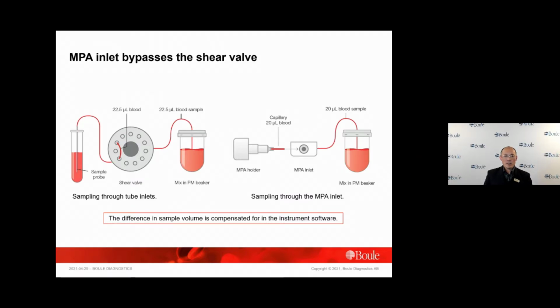The instrument is also equipped with the MPA module, where the user can sample directly from a fingertip or from a smaller sample tube to make the measurement directly inside the instrument. And here is the microtube instead of the shear valve to take the whole blood volume.